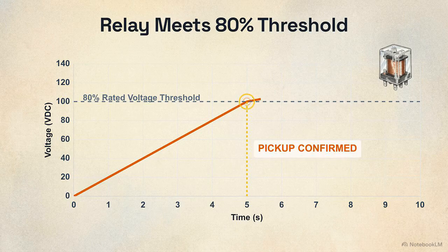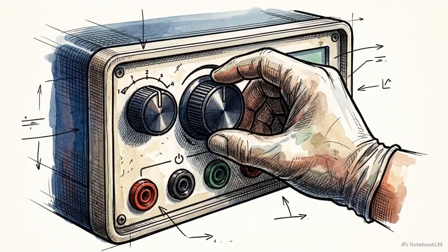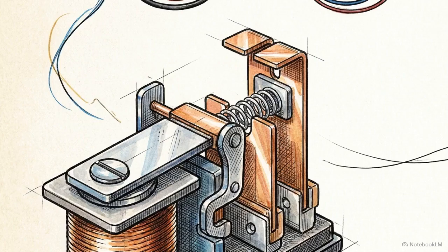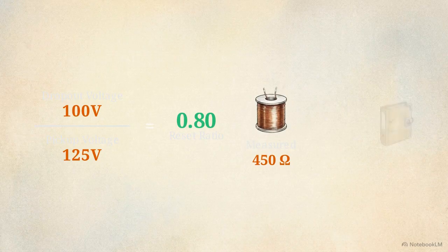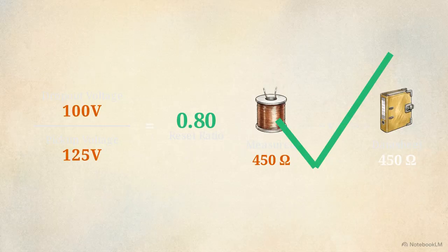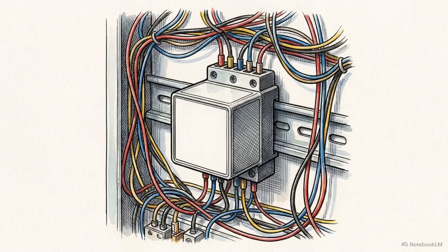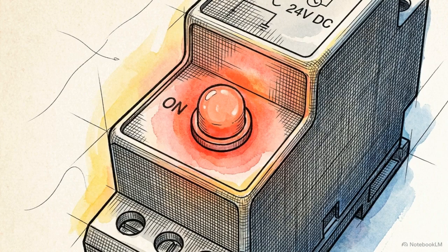For many supervision relays, this mechanical action must occur at exactly 80% of the coil's rated voltage. The technician then reverses the procedure, slowly decreasing the injected voltage. They record the dropout point, capturing the exact voltage level where the contact releases and opens the circuit. By comparing the pickup and dropout voltages, engineers calculate the relay's reset ratio. They also measure the internal coil resistance to ensure it matches the original factory datasheet, proving the windings haven't degraded. Establishing these precise voltage thresholds prevents the relay from nuisance tripping during minor power fluctuations, while guaranteeing a hard-coded response when genuine voltage sags occur.